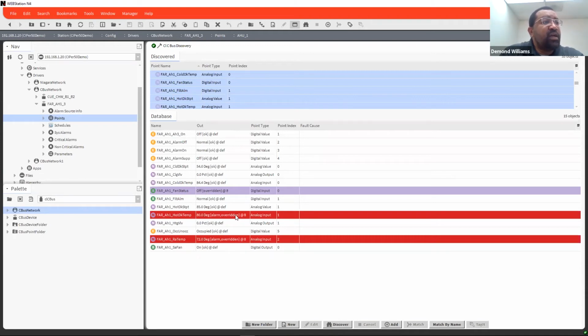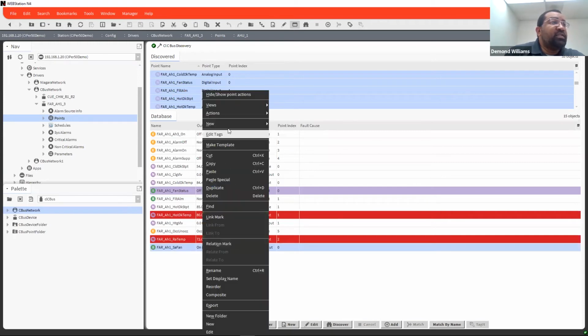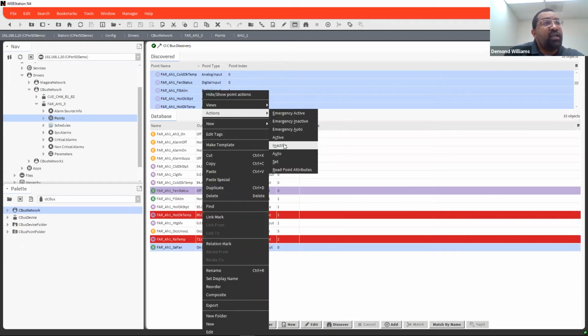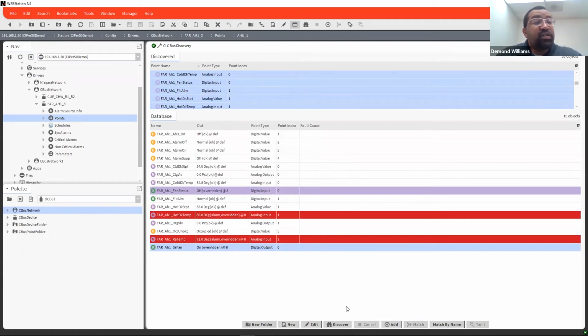And at this point in time, I have these points here. I can actually go in and instantly go to action and start overriding data points in here. The good thing about this system, there is no lag. So as soon as I push the OK to tell this fan to go off, the unit actually does go off, so you don't have to worry about that. Anything of a lag, maybe up to a minute or something like that, when you have other third-party drivers that actually tie into the Honeywell C-Bus as well. So are the points writable? Yes, they are.